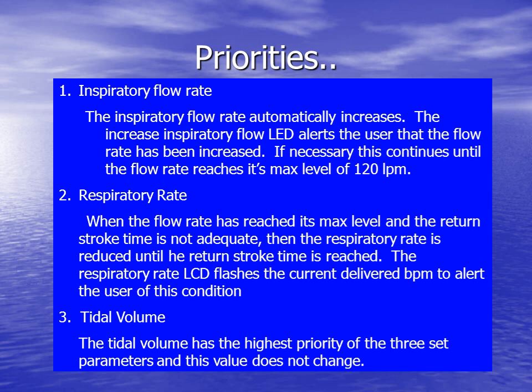If you have set ventilator parameters that the vent is physically unable to deliver, the vent prioritizes them in this order. The tidal volume has the highest priority, and this value will not change. Respiratory rate is second and will be automatically reduced to the number that the ventilator is physically able to deliver. Inspiratory flow rate is the first to change. The vent will manipulate it first to try and deliver your set parameters. Again, it is capable of delivering up to 120 liters per minute of inspiratory flow.